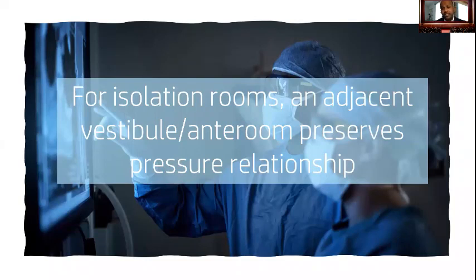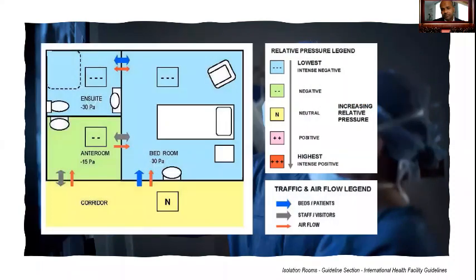Airflow direction, as I mentioned earlier, is especially crucial for healthcare facilities, where this can be achieved through a pressure difference. Isolation rooms with COVID patients or rooms where aerosol generating procedures are performed should use negative air pressure. Now, in order for negative air pressure to work, it is recommended to have an anteroom or a vestibule to preserve the pressure relationship. Here is a typical pressure isolation room with anteroom and ensuite showing airflows and relative pressure.